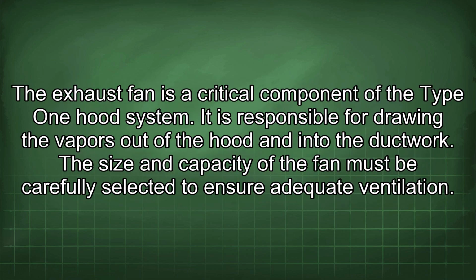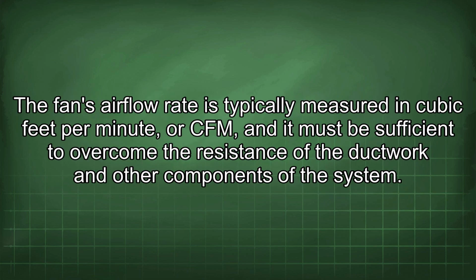The exhaust fan is a critical component of the Type 1 hood system. It is responsible for drawing the vapors out of the hood and into the ductwork. The size and capacity of the fan must be carefully selected to ensure adequate ventilation. The fan's airflow rate is typically measured in cubic feet per minute, or CFM, and it must be sufficient to overcome the resistance of the ductwork and other components of the system.